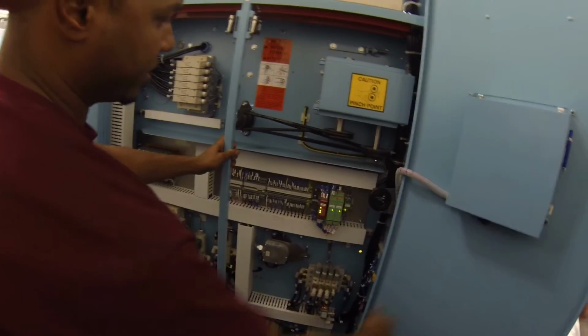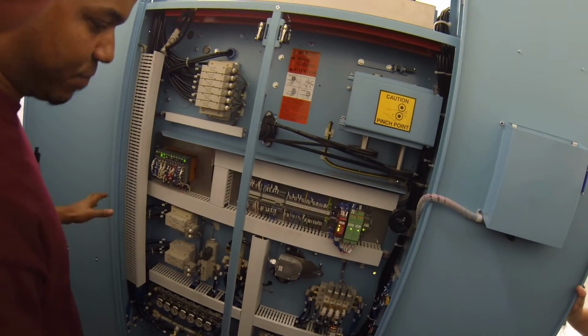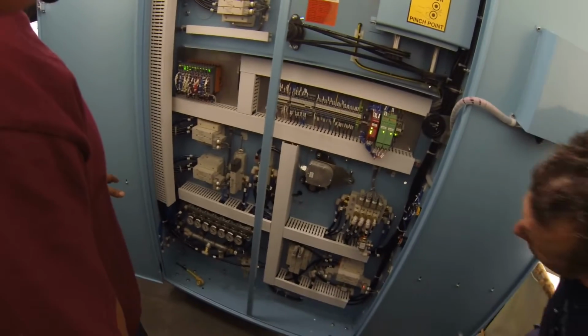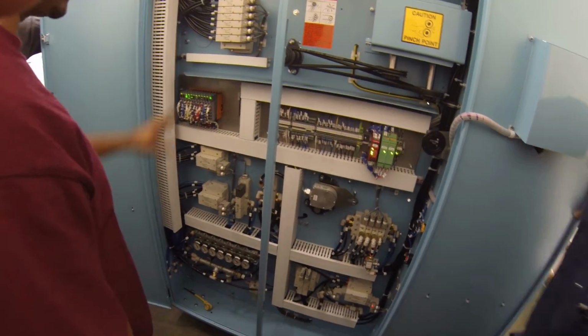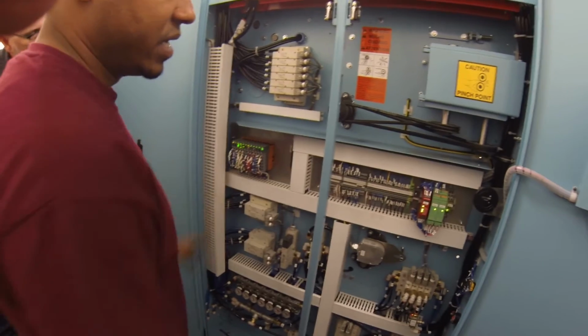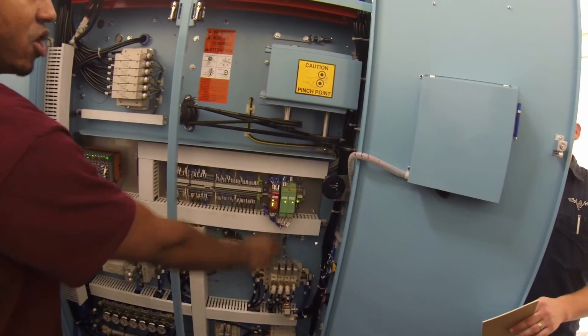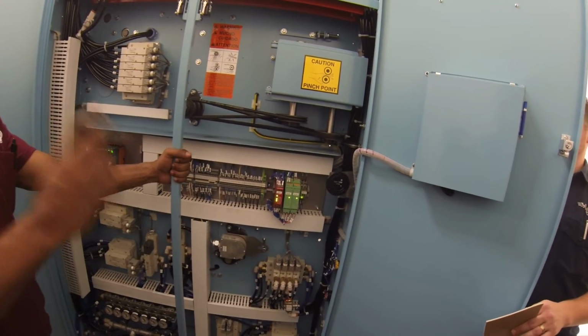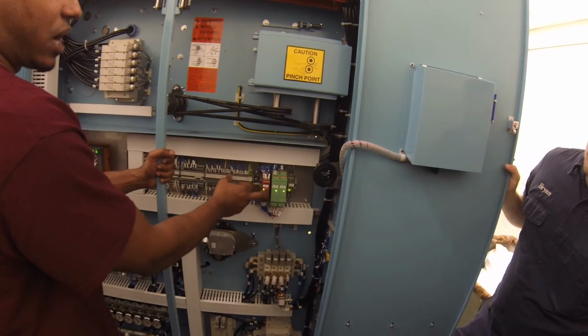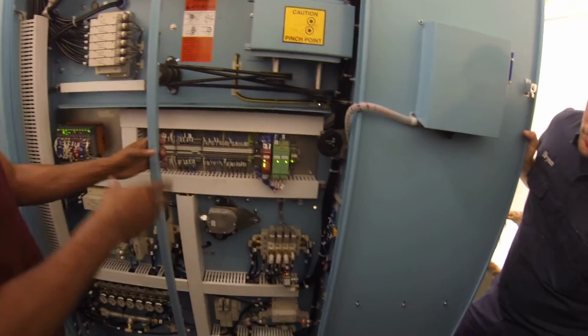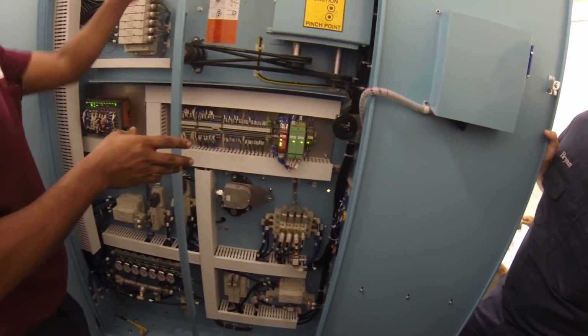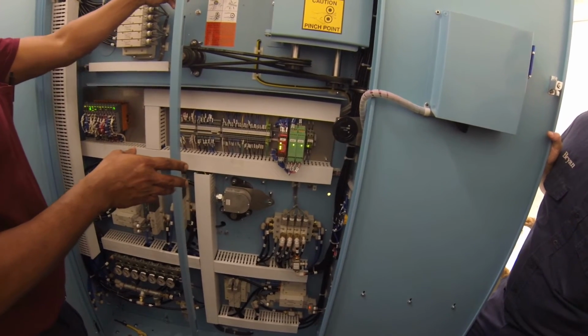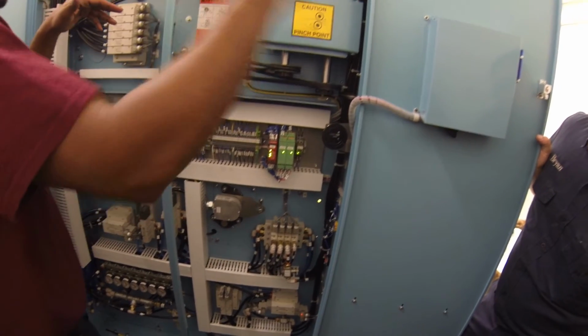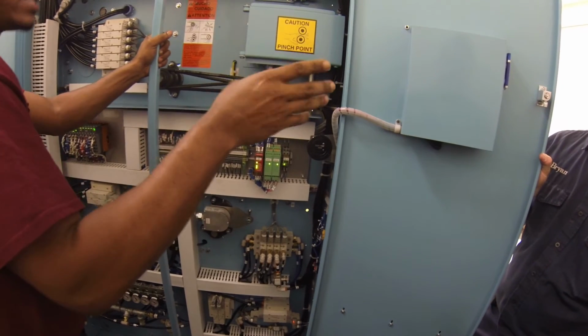Like I said earlier, it's a pretty simple system. What we have is just pneumatic, PLC that runs everything. This is the safety circuit there. The first day when we had the issues, we were never getting that SR1, so one of the safety interlocks was not made.